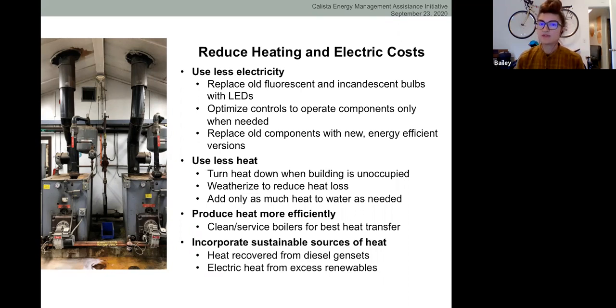Some examples: rather than pumping and circulating water in distribution loops all year, only circulate it during the heating season. Or rather than letting a heat tape run all winter, automate it to operate only below a certain temperature threshold, or only when water is not moving in a particular line. So sometimes, even without changing components, we can make a big difference by changing how things are controlled.